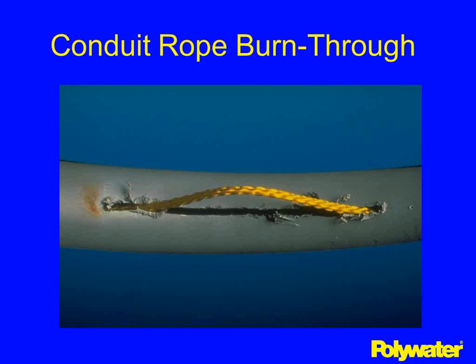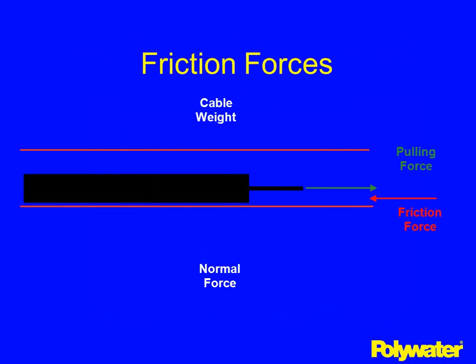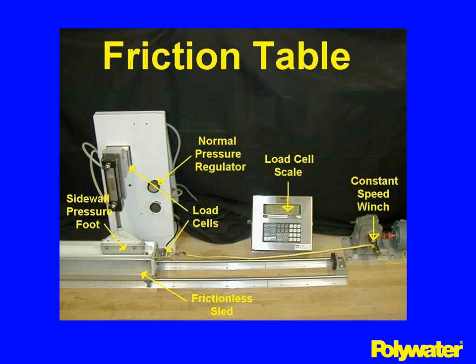Let's talk about coefficients of friction — what is the definition and how is it measured? Looking at frictional forces: if a cable weighs 10 pounds per foot, there is an equal normal force pushing up on the cable. When we pull the cable, the pulling force tries to overcome the frictional force — the difference between the cable jacket and the conduit surface. By general laws of physics, if the cable weighs 10 pounds per foot and it took 5 pounds to move it across the conduit, the coefficient of friction would be 0.5.